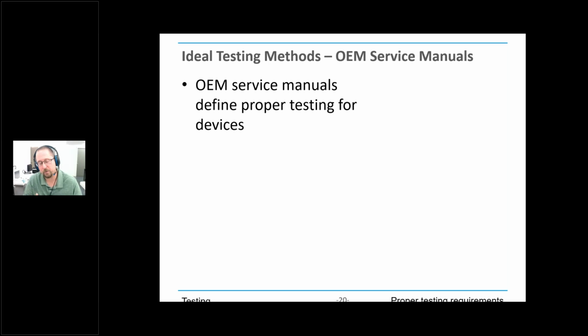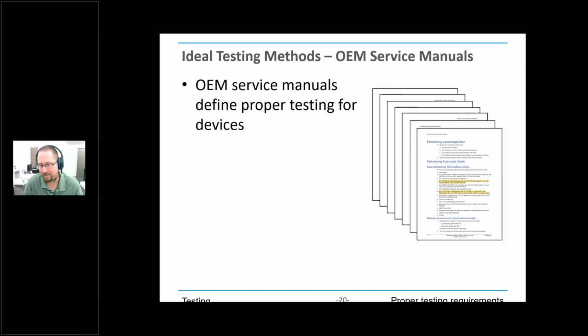So ideal testing methods really are defined in service manuals. In our research, we came up with some other tests that would be great to do, but really the OEMs spend years developing these technologies, and they know where they're going to fail, and that's why they put these tests in the service manual, because they want to make sure that the devices are working properly. So we really just need to use what's in the service manual, if at all possible. We did not discover any new additional tests that would be any better than what's in the service manual.